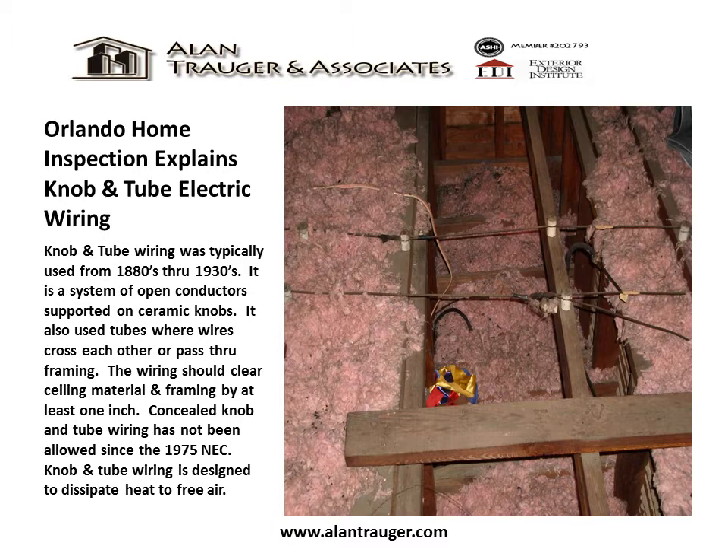The wiring should clear ceiling material and framing by at least one inch. Concealed knob and tube wiring has not been allowed since the 1975 NEC.